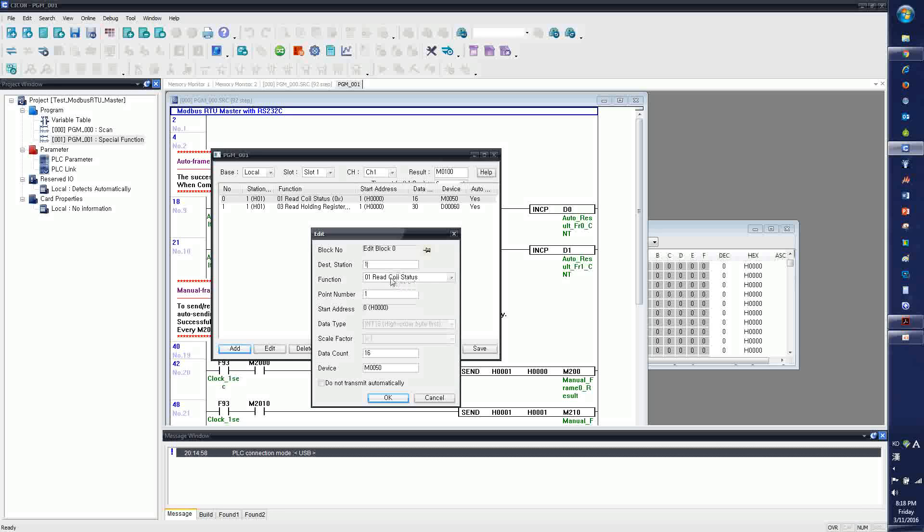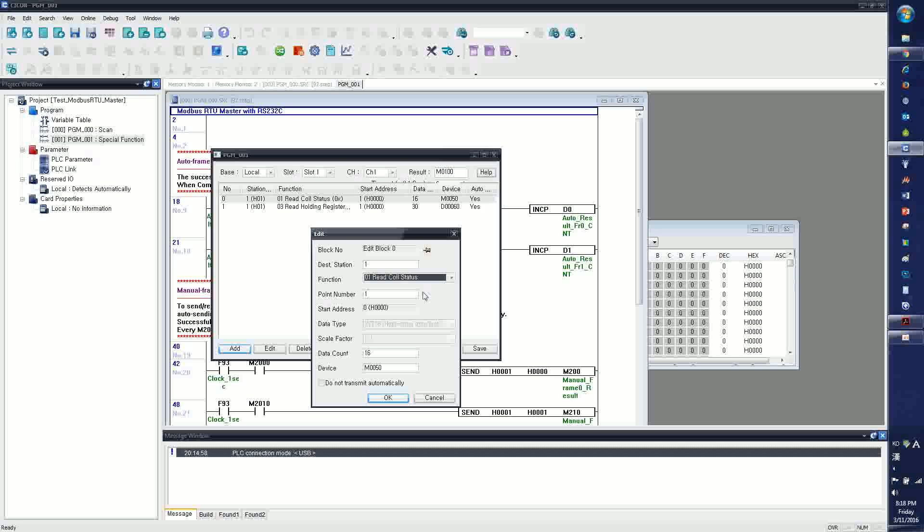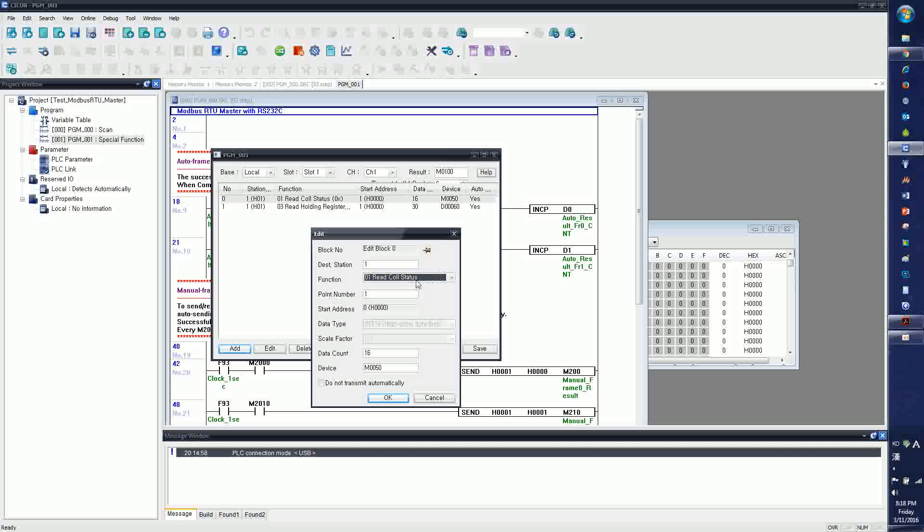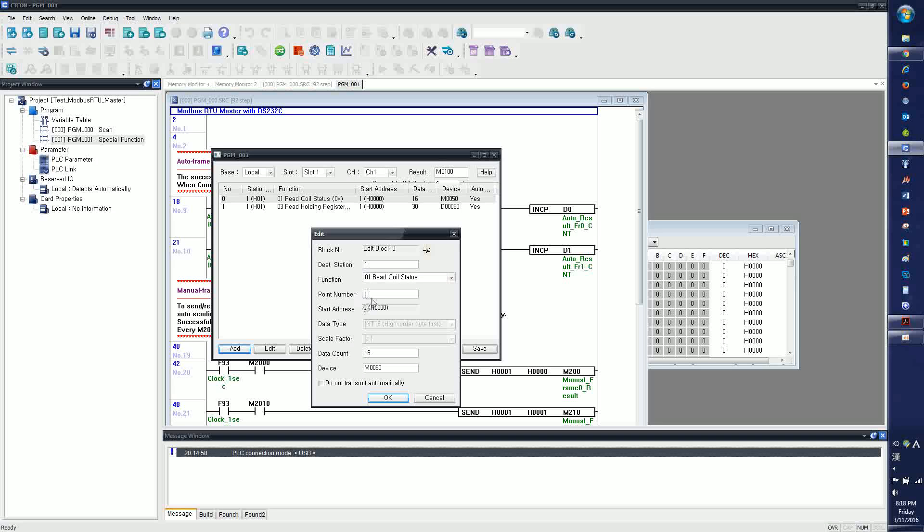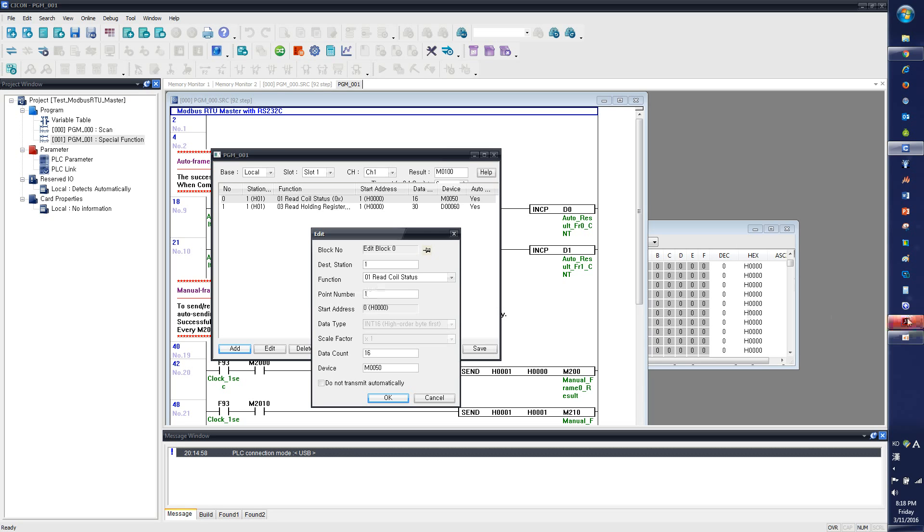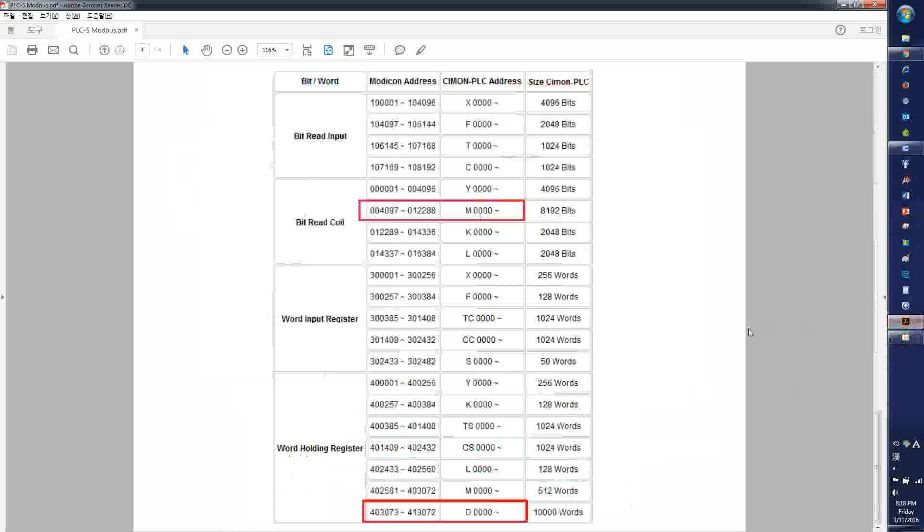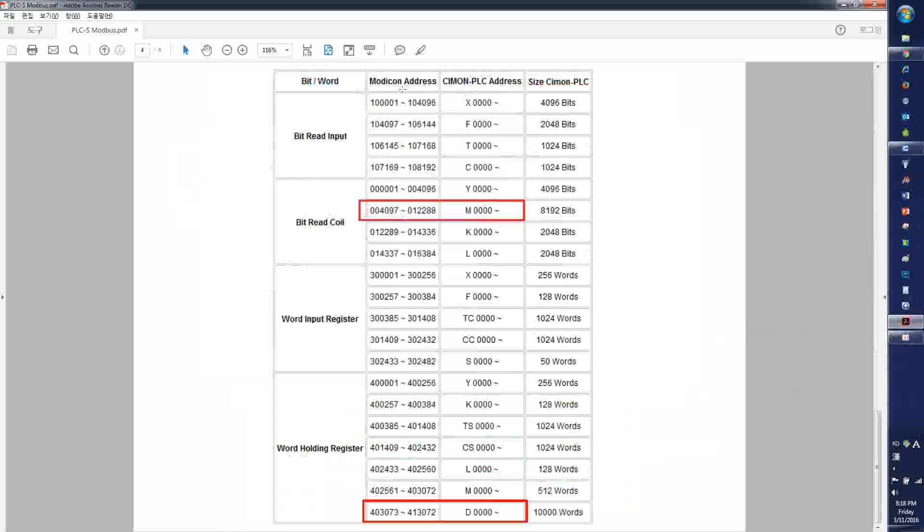The function, we have six functions available, but this one, the first one, the read coil status, is to read the bit address. So I've chosen the read coil status, and the point number, which I will explain later, also on Modbus slave configuration. This will link the Cimon PLC address and the Modbus address.